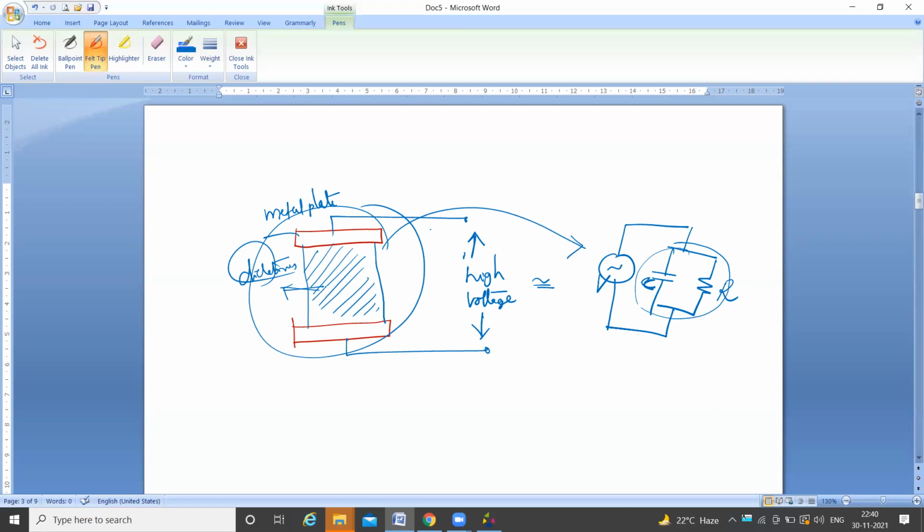And here, electrodes are used in electric heating, and different types of electrodes are used depending on the material to be heated. When the material travels between the electrodes on a conveyor belt, the material is non-uniform in dimensions, or different parts of the material are required to be heated to different states, then an air clearance is permitted between the dielectric material and one or both of the electrodes. The shape and size of the electrodes between which the material to be heated is placed depend upon the fact that a uniform voltage gradient has to be provided.